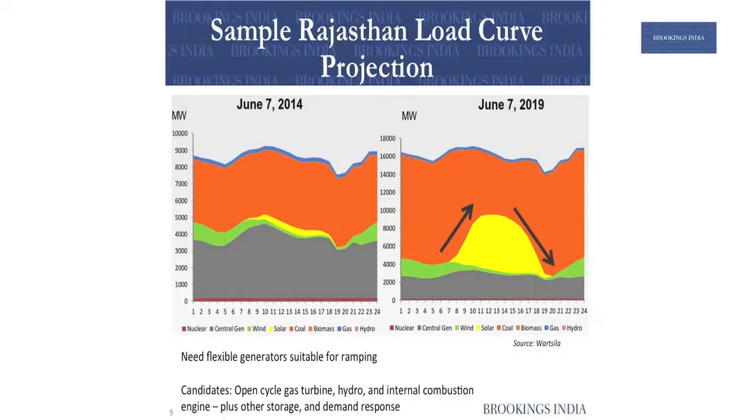Now if you overlay it, looking at coal and RE, this is a curve showing 2014 real data and extrapolating to 2019. Right now solar is a small portion, but as solar grows as per projections to X thousand megawatts, we see that it creates a ramp-up and a ramp-down requirement. Either coal will have an implication on its plant load factor, or we need other generators suitable for ramping — typically one of three: open cycle gas turbine, hydro, or internal combustion engines. And of course people also talk about storage and demand response as other candidates.